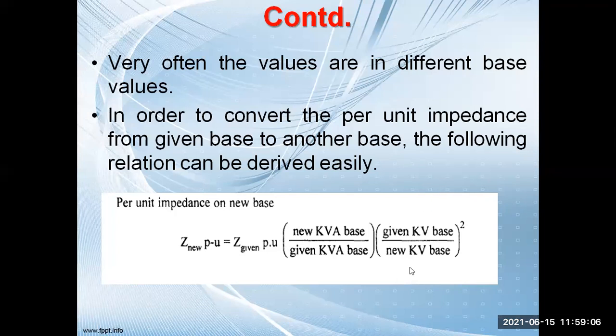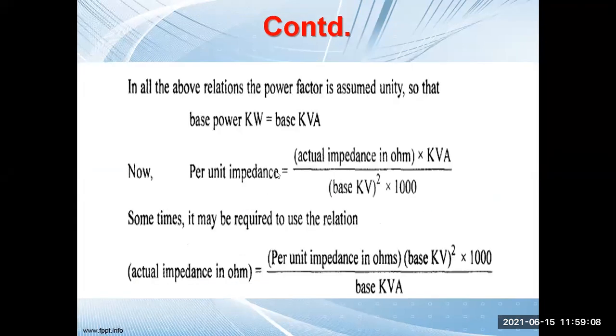Now we'll explain this formula. This is per unit impedance: Z given equals actual impedance in ohms, into kVA, divided by base kV squared, into 1000.